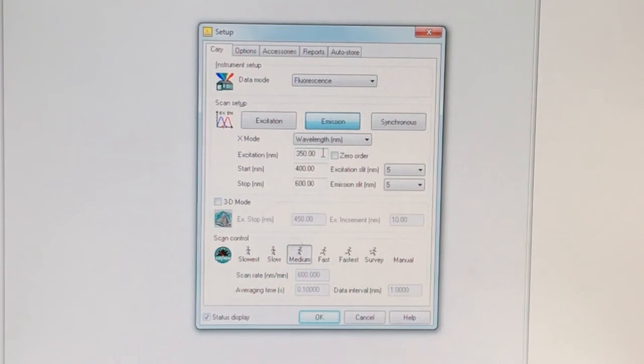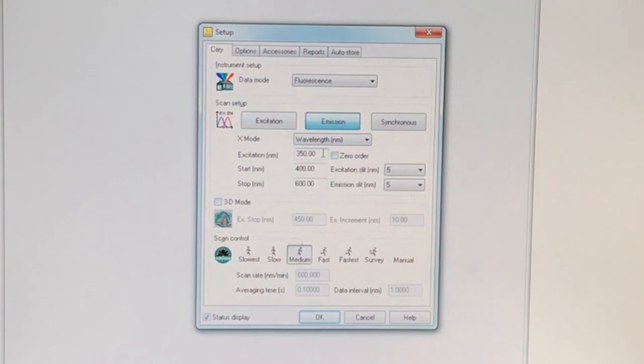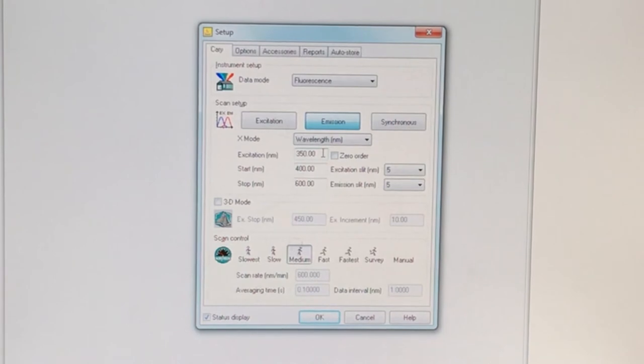The PMT is very sensitive. We don't want a lot of light hitting the PMT. Our excitation source is very bright. And so if our scan is going to overlap with our excitation source, we get a lot of light impinging on the detector. And that's bad for the detector.